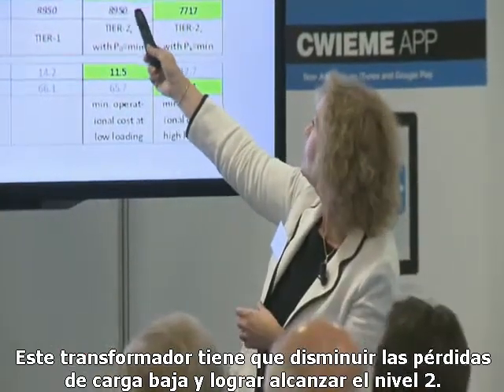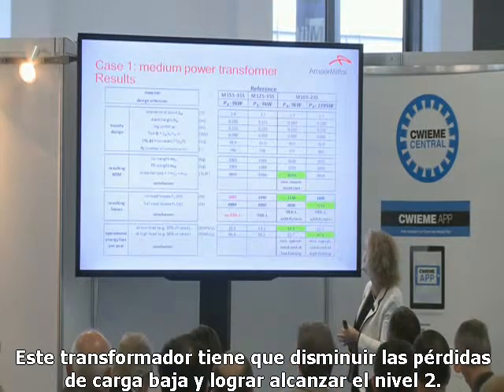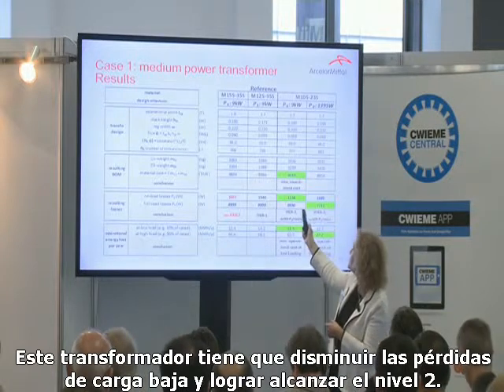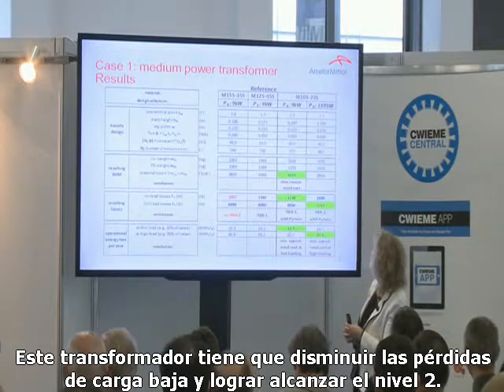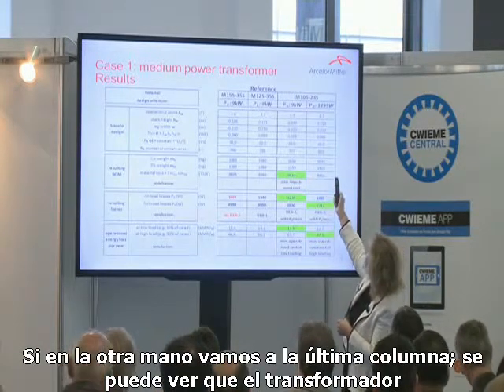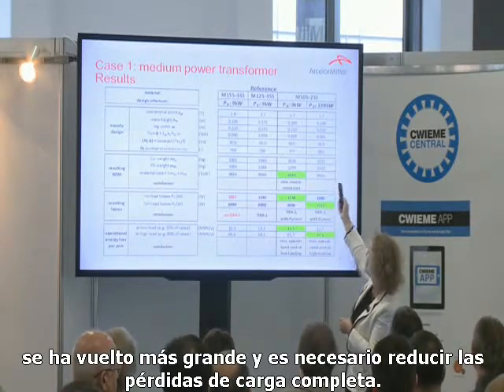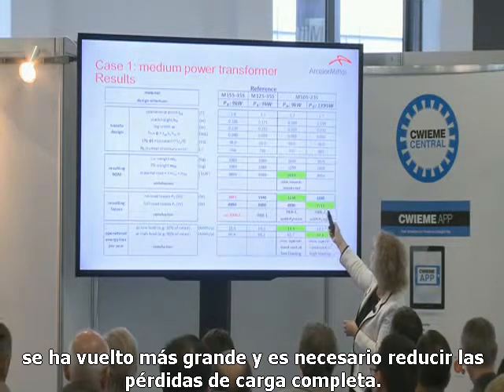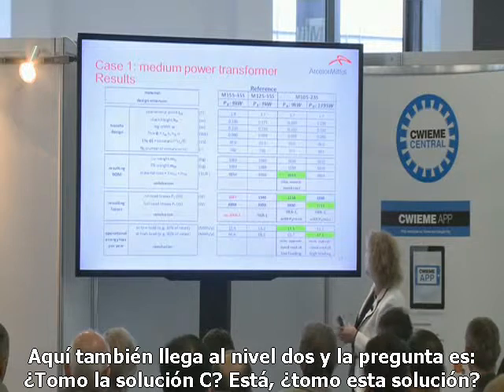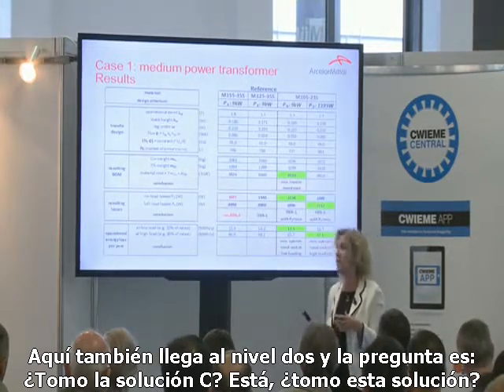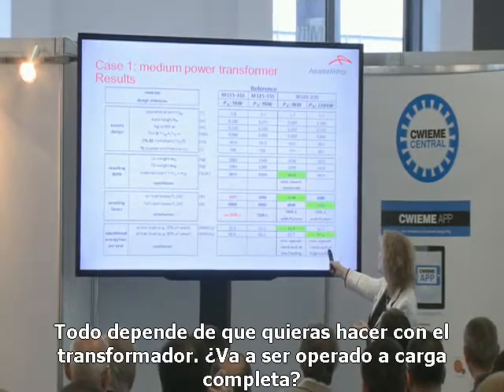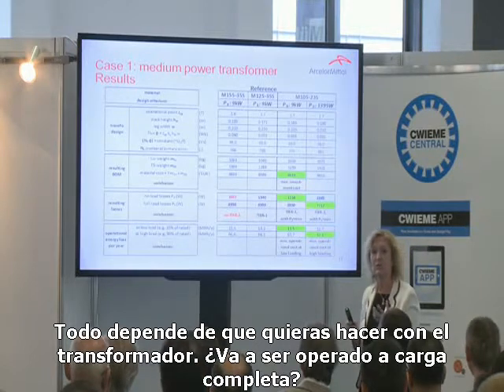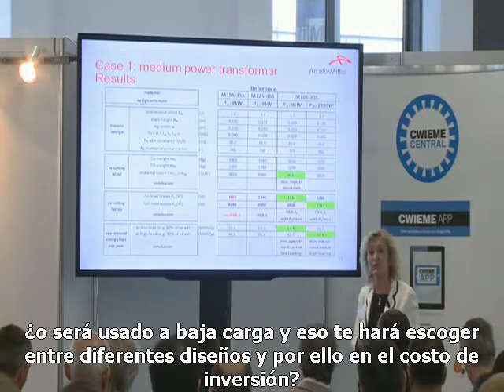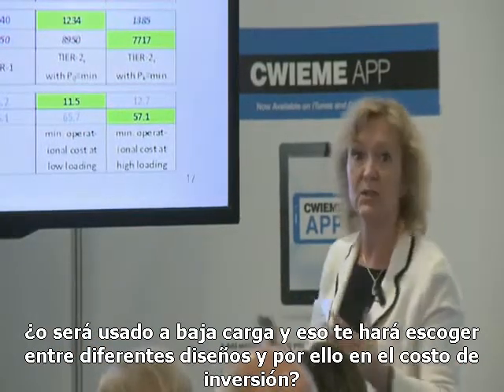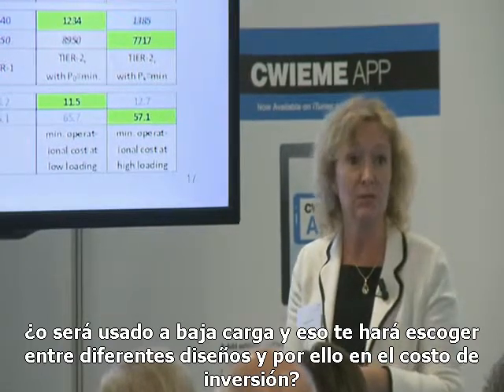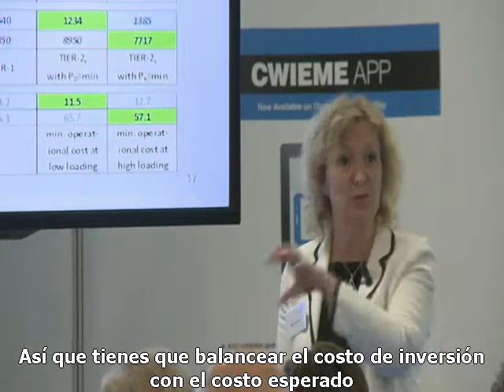This transformer so has the lowest no load losses, and it manages to reach the tier 2 targets. If you then, on the other hand, go for the last column, you can see that the transformer has become bigger, and this is necessary in order to further reduce the full load losses. It also reaches the tier 2 target. And the point really will be, do I take solution C, so this one, do I take this solution? It all depends on what you want to do with your transformer. Is it going to be very much operational, not full load, or is it rather going to be used at lower load levels? And that will make you choose between the different designs, and hence in the investment cost. So you have to balance the investment cost with your exploitation cost.